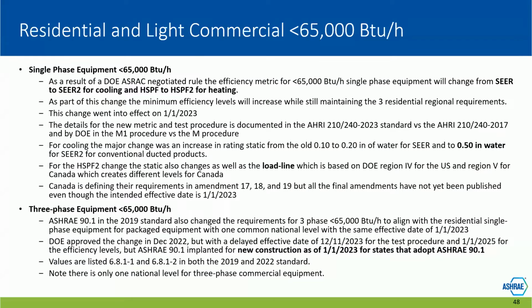But one of the bigger changes, as you can see down there in the 4th bullet, is the change in the external static. That's something that the industry has kind of been on the low side for us. Statics are in the 0.1, 0.2 for residential equipment, and they raised them up to a 0.5. So that increases your fan power, it decreases your efficiency. They also changed some of the load lines for the heat pumps and address the cold climates. We hear a lot about cold climate heat pumps. I'm actually sitting in Canada right now, so we were talking about that today. And, as to where they're going.